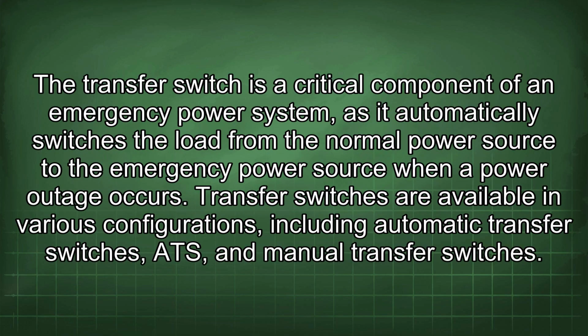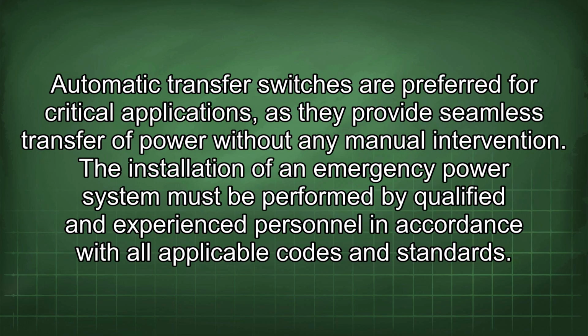The transfer switch is a critical component of an emergency power system, as it automatically switches the load from the normal power source to the emergency power source when a power outage occurs. Transfer switches are available in various configurations, including automatic transfer switches (ATS) and manual transfer switches. Automatic transfer switches are preferred for critical applications, as they provide seamless transfer of power without any manual intervention.